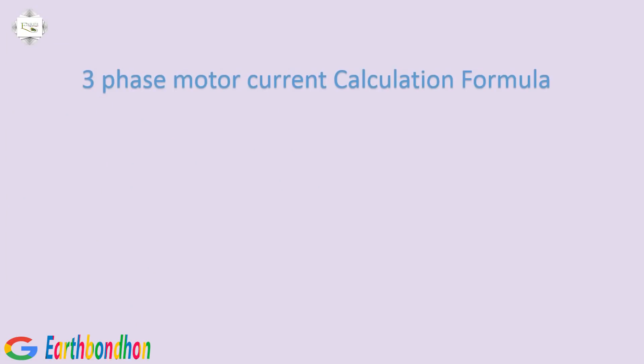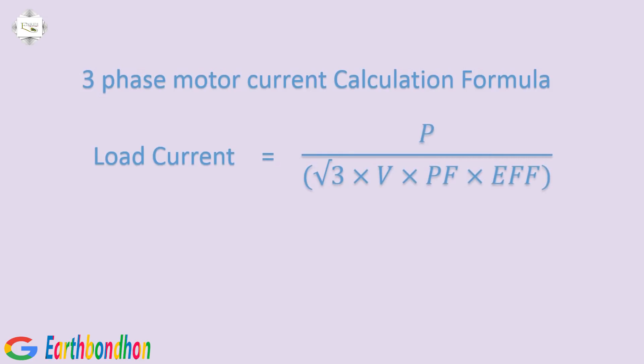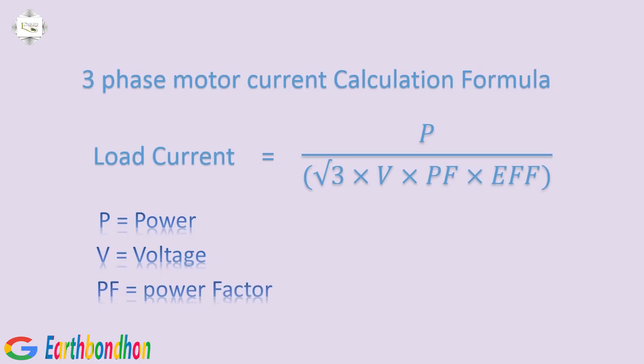Three-phase motor current calculation formula: Load current equals P divided by square root of three, multiplied by V, multiplied by PF, multiplied by EFF. Where P equals power, V equals voltage, PF equals power factor, EFF equals efficiency, and square root of three equals 1.73.